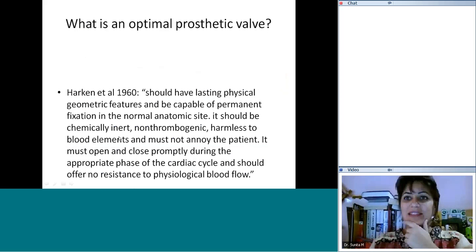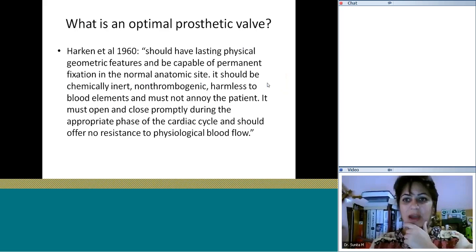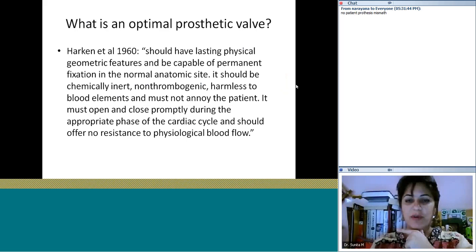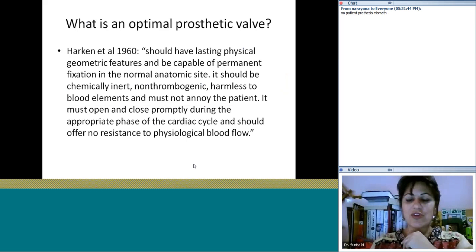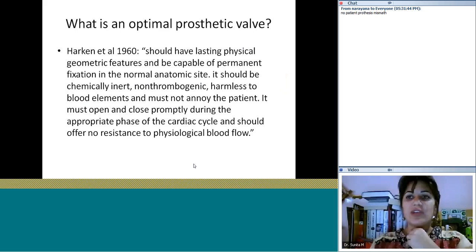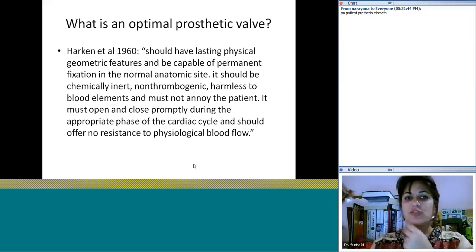Three answers: less thrombogenic, durable, and an ideal profile. From 1960, Harken said it should have lasting physical and geometric features, be capable of permanent fixation, be chemically inert so the patient doesn't react against it, non-thrombogenic, harmless, and should open and close promptly during the appropriate phase. So the ideal prosthetic valve should have a low profile, last a long time, be non-thrombogenic, and body tissue should not react against it.